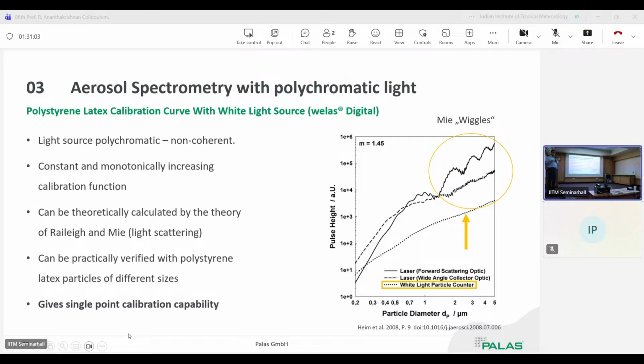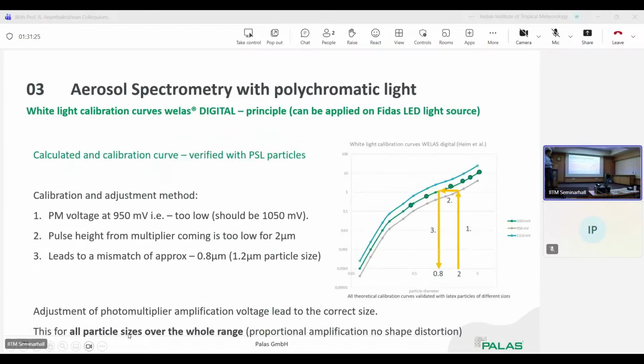So you adjust the photomultiplier voltage so that the signal coming from the photomultiplier fits the calibration curve and the respective size of the particles you suspended. This is normalized, and we know the optical size of those particles, which we have tested before. So we have different calibration curves for different photomultiplier voltages. For example, the correct setting would be 1050 millivolts for the photomultiplier voltage in order to size particles correctly.